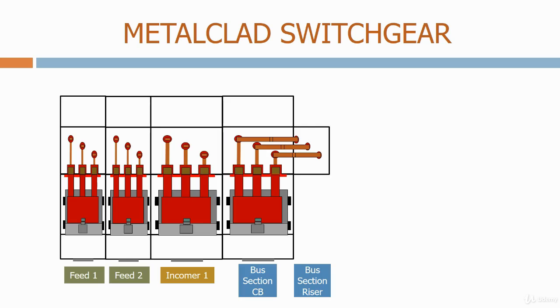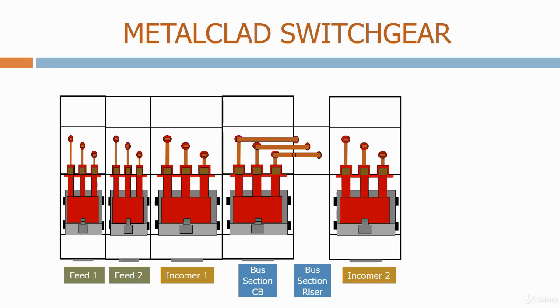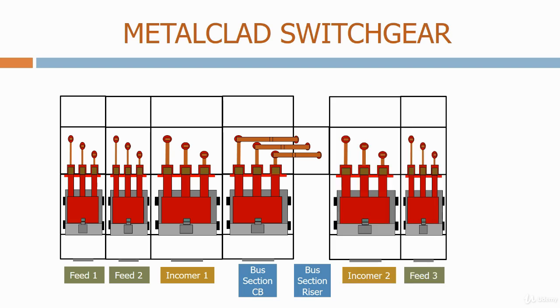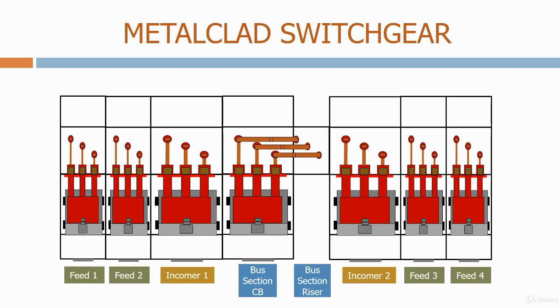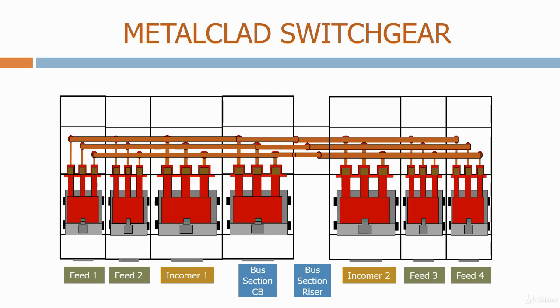After the bus section riser panel, we now carry on with incomer 2, feeder 3, and feeder 4. We've now completed the second bus bar. We then run bus bar 1 all the way over from feeder 1 to the bus section chamber, and bus bar number 2 from the bus section riser chamber all the way over to feeder 4. We've now implemented the single line diagram.